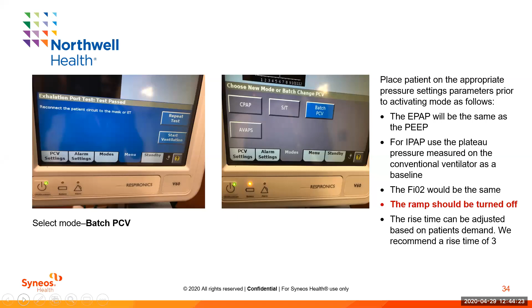So AVAPS we went over earlier. It's a volume targeted mode of ventilation that'll move between set pressure parameters, no less than X, no greater than X times 2. And it'll set a rate and an inspiratory time to deliver the set flow. The ST mode of ventilation, you'll be setting a rate, inspiratory pressure and an expiratory pressure. This particular machine calls them IPAP or EPAP. And then you can choose batch PCV, which would be typical to standard pressure control ventilation.